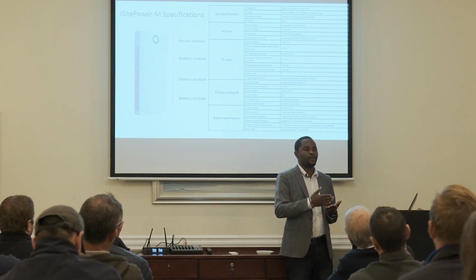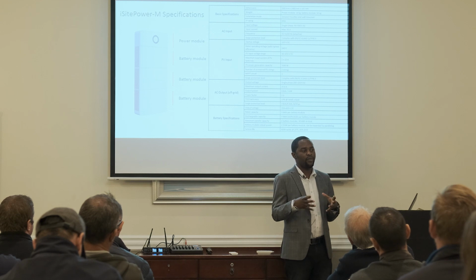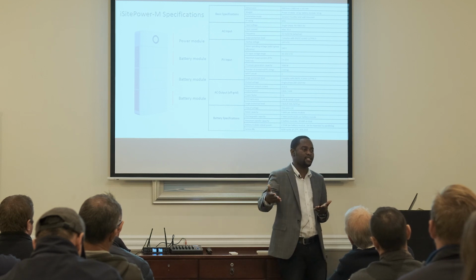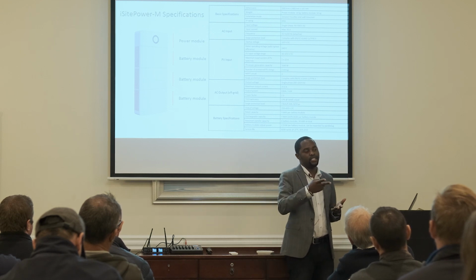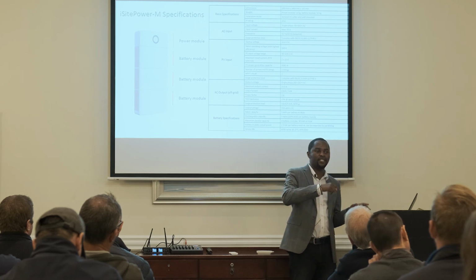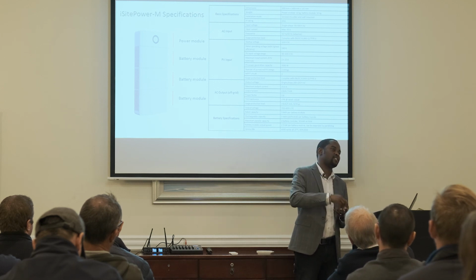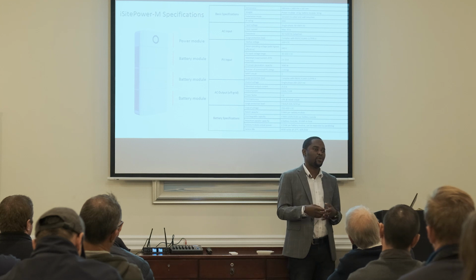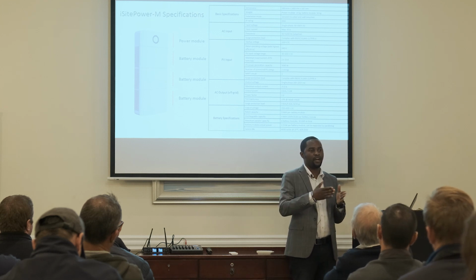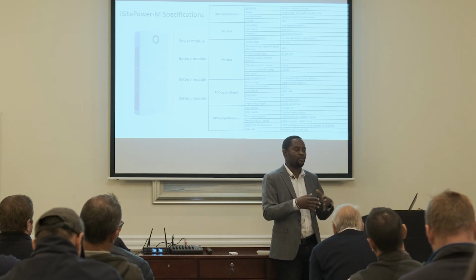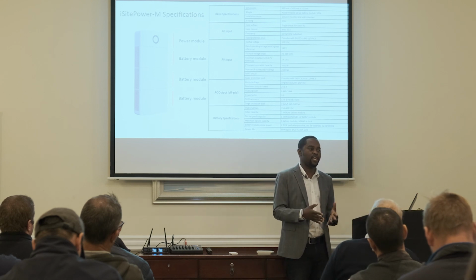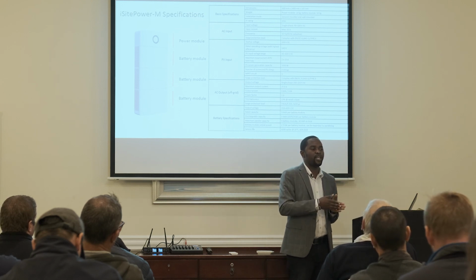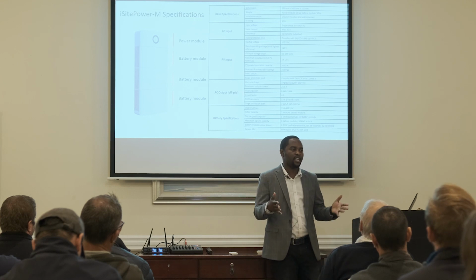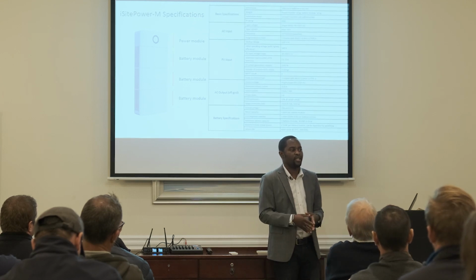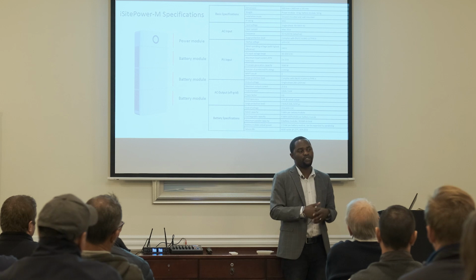But remember, when they were adapting it from the sites to the residential, they changed the BMS on the charge. So you can charge it at 1C, but you can discharge it at 0.5C. Which is also a great thing. So if you've got frequent load shedding periods, let's say 4 or 5 load shedding periods per day, when the grid comes back, you can charge it quickly. If grid is available for an hour, your batteries are full again. But when you are discharging, then it drops to 0.5C.